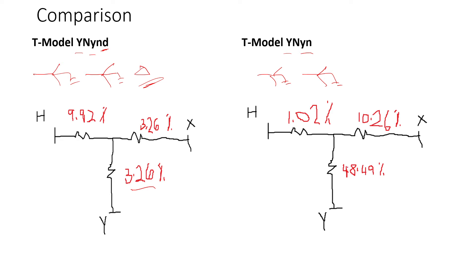So notice when I had the delta, look at this value here versus if I don't have a delta. The delta basically, you see it lowered this impedance, and that's one of the purposes why this delta here is included, because you want to lower that impedance. So in a sense this here, it's 48%, I mean it's not huge, it's not infinite, but this can be thought of as it's like it's open. Basically you have the side here but it's open to ground, because it's a big impedance basically.